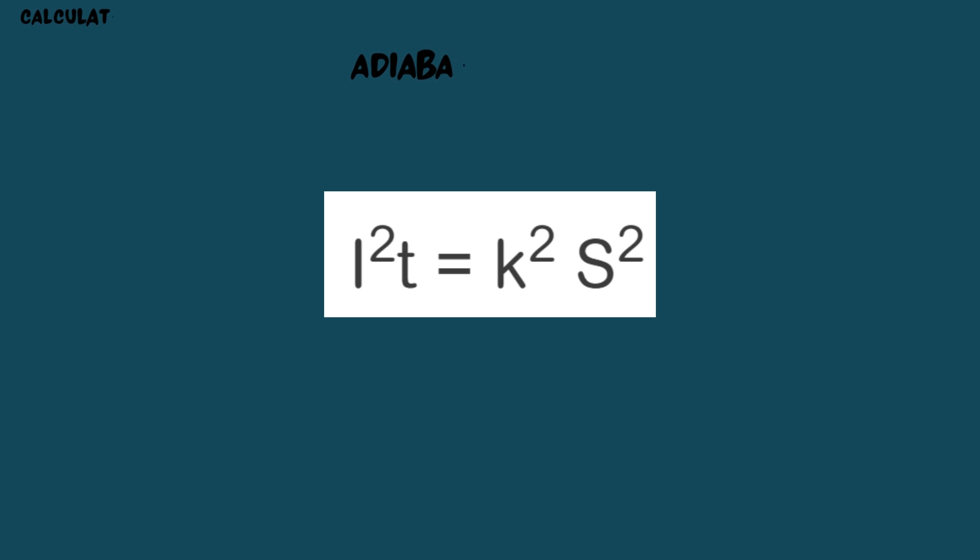The adiabatic method is used to calculate the minimum conductor size when heat loss from the current-carrying component during the short-circuit is neglected. This is a conservative approach that is valid for short-circuit durations of up to 5 seconds.